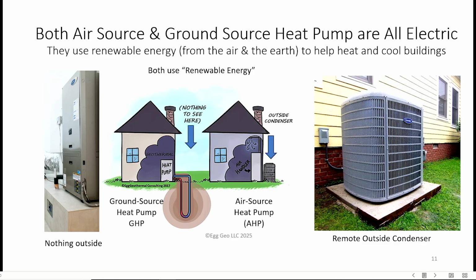This is a Carrier unitary geothermal heat pump here. They are exactly the same technology. Nothing different, no cost difference, nothing different with the equipment. The only difference is they took the compressor, which is about the size of an oblong basketball, out of here, put it in here, and in place of all these coils out here, these are air-cooled fins, they put what's called a coaxial heat exchanger that's about this big, and it's about that thick, and it's got a hole in the middle, and it mixes the temperature of the refrigerant and the water going down in the ground, just the temperature, through a double wall coaxial exchanger, and that's how it takes the place of the air coil. So all that is now in this bottom section, the compressor, the refrigerant to water exchanger, and so that is now shoved into here, and this is the whole thing.